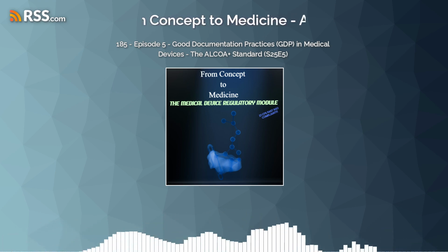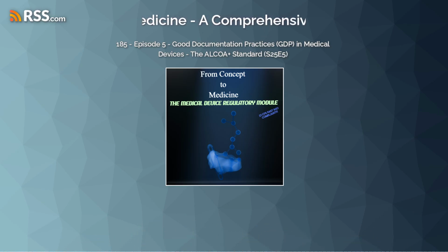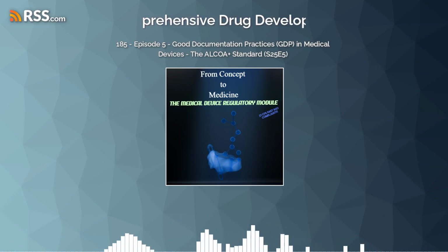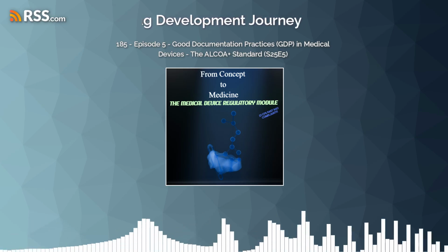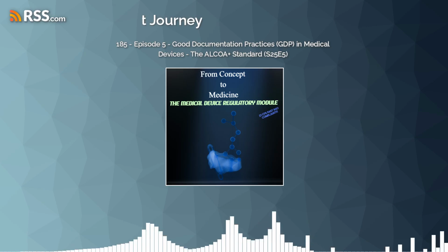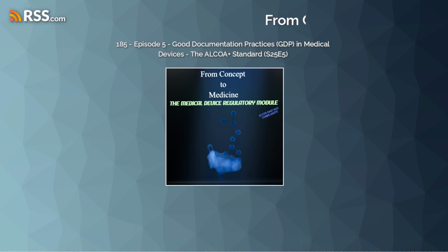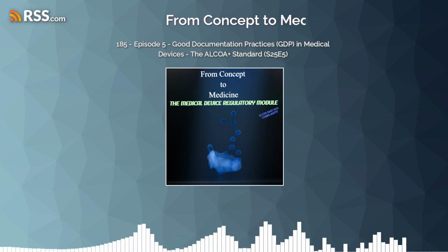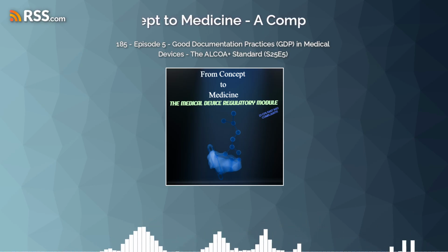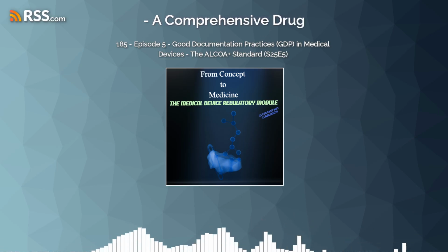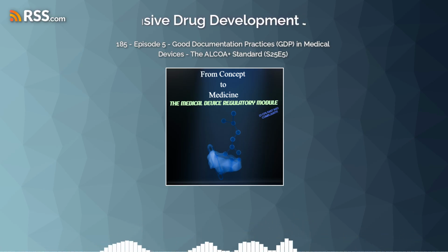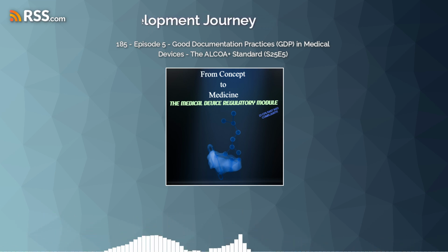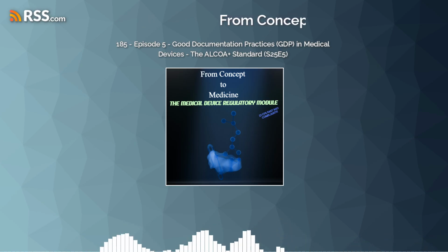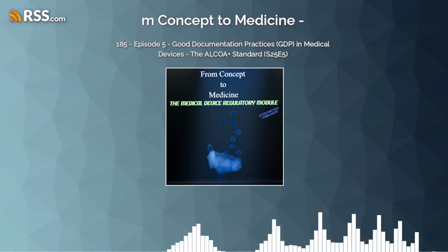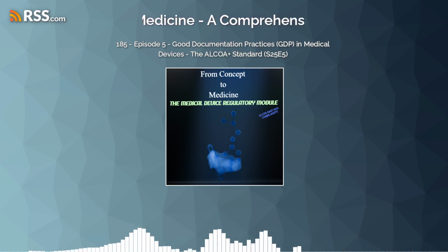Right. These three are crucial. They're distinct, but they're also deeply linked. Think of them as maybe different chapters telling the story of the device. Okay, chapter 1. Chapter 1 is the design history file, the DHF. This is required by FDA 21 CFR Part 820.30. Essentially, it's the complete story of how the device was designed. It bundles together all the records from the design and development process: your design plans, the inputs, like what the device needs to achieve, the outputs, the actual specifications, design reviews, risk analysis, verification testing, did we build the device right according to the specs, and validation testing, did we build the right device for the user's needs, plus how that design was transferred to manufacturing. It shows all the thinking and testing behind the design.